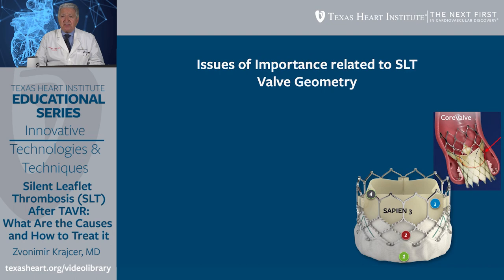Sapien 3 is suited for annular deployment, whereas CoreValve is self-expanding with a nitinol stent frame and porcine leaflets. The newer generation CoreValve also has external porcine material wrapped around the nitinol frame for prevention of perivalvular leak.